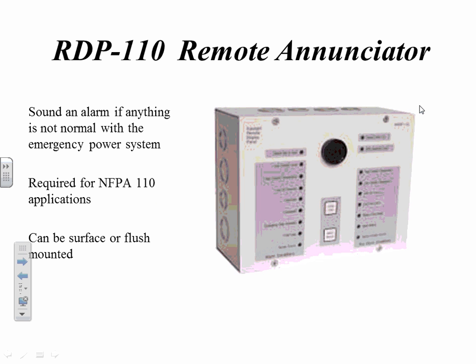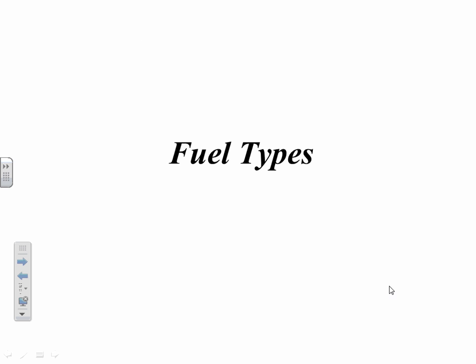And here we have what we call the RDP 110 remote annunciator. All generator sets typically today will have a remote annunciator, so you can immediately tell if there's an issue with the generator set. Even if you move the control on the generator to the off position for maintenance, do an oil change or whatever, you'll have an alarm that comes on this thing, so they know things are being worked on. And this is required by NFPA 110 applications, any legally required system.